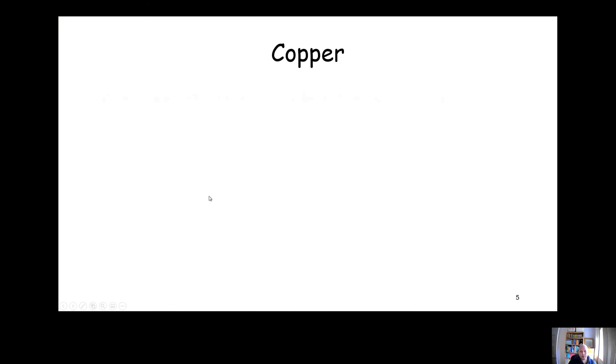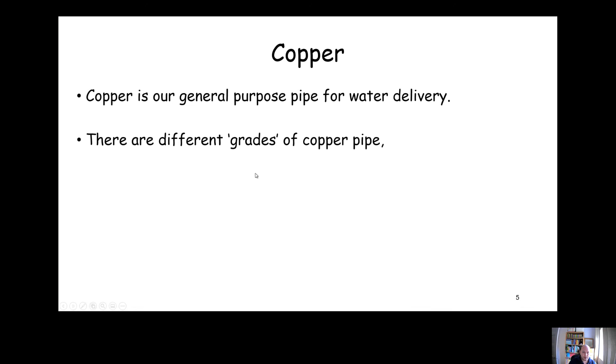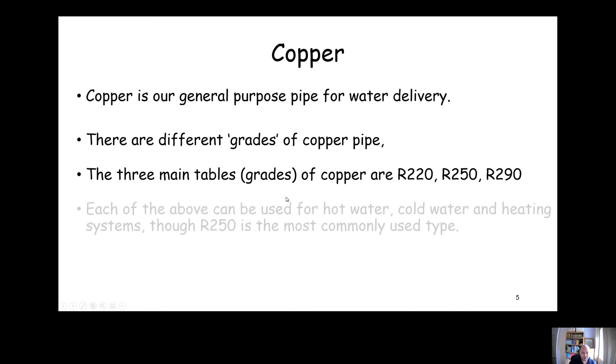Copper is a general purpose pipe used for water delivery. There's three different grades of copper, some people call them tables of copper: R220, R250, and R290. We can use each of them for hot, cold, and heating, though R250 is the most commonly used type.